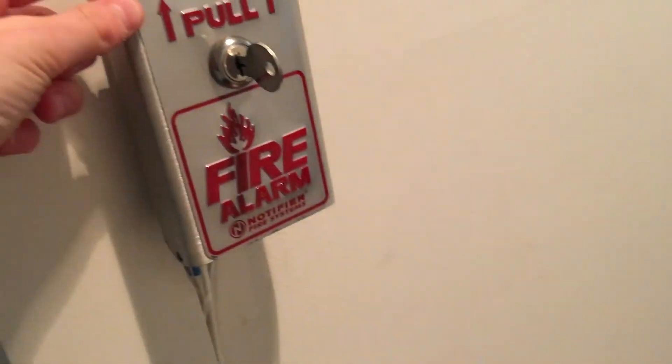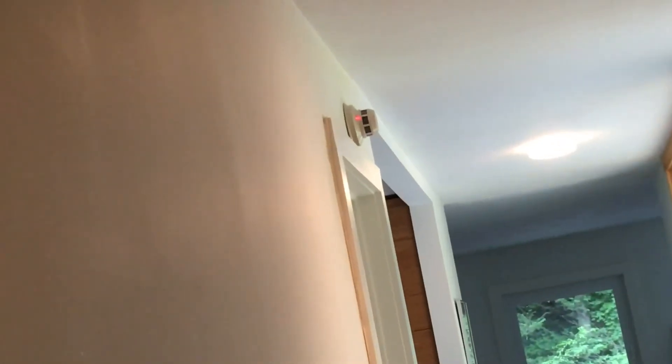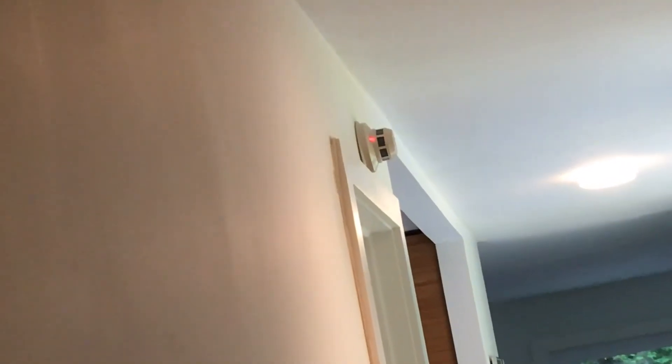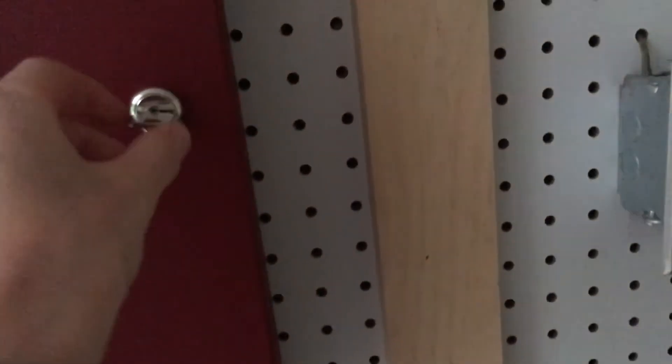So one thing I realized is if you were to pull this pull station, which is on the same zone, that light would go off. I'm not really quite sure if you can see the light. You can. All right, so I'm going to pull it and then you'll see it go off. See? Sorry about the zoom. I'm really sorry about this. I'm having trouble with the zooming on this. Oh, there we go. All right, and let's reset it.